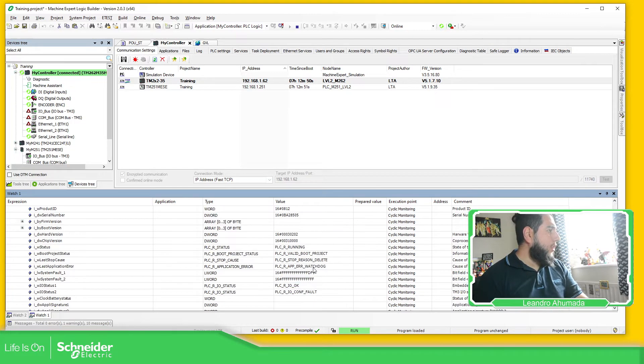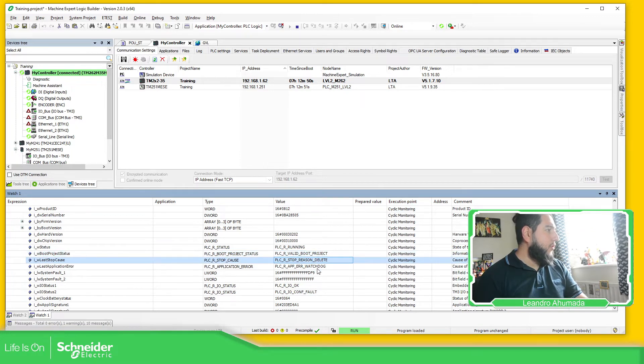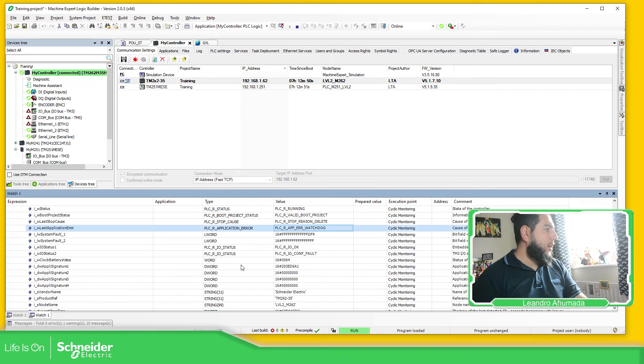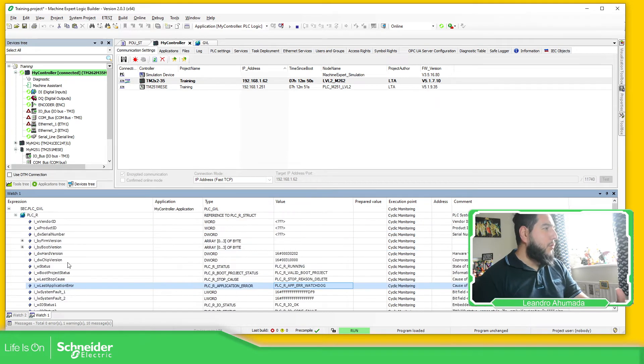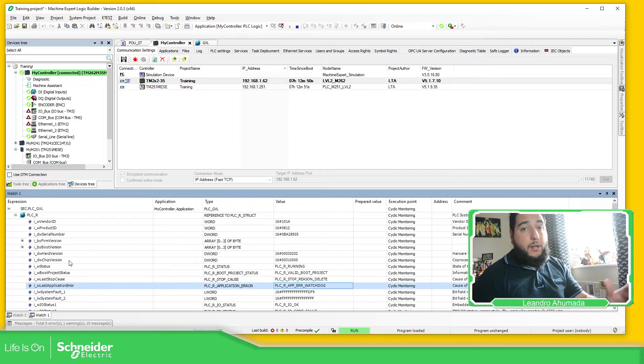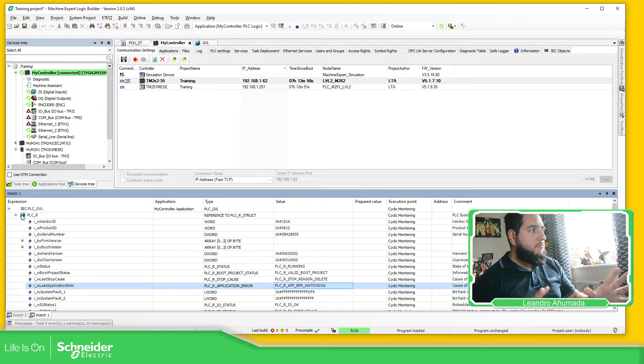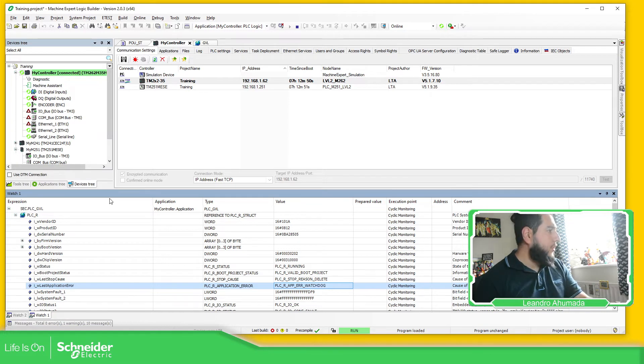Once you do this, you should be able to see the complete list of information that we are able to use. So PLC underscore R — you can see PLC running, valid boot project, last stop cause, application error, watchdog. You can see this information, and if you want you can share that with a screen or another device. So this is how you can access and have an overview of what's going on in the controller.